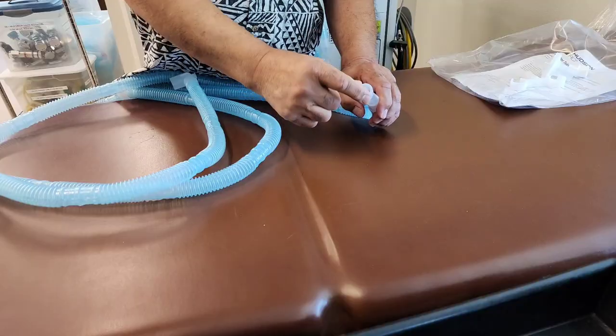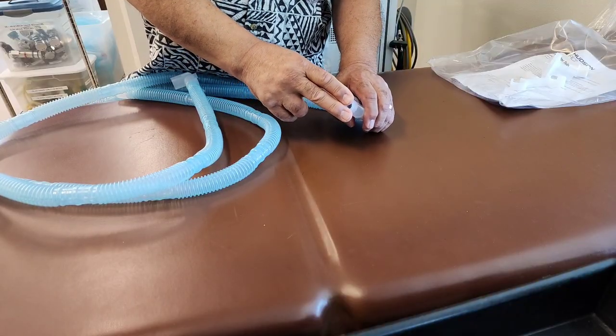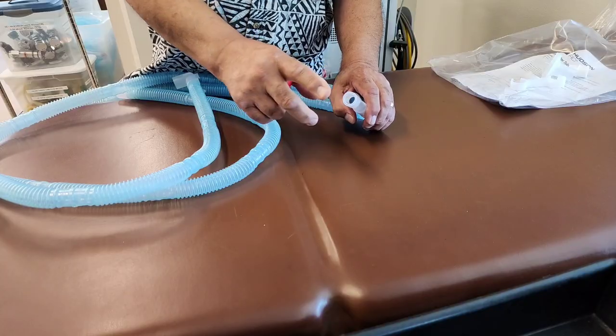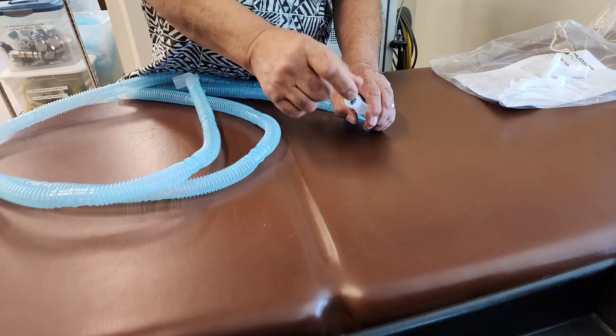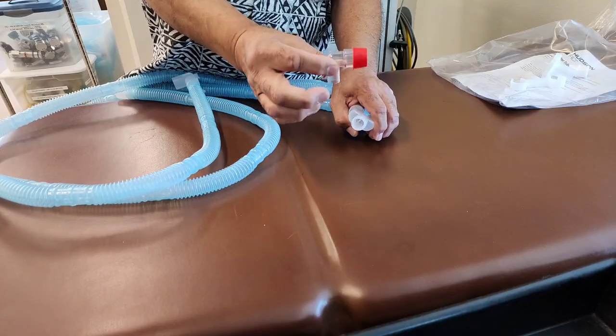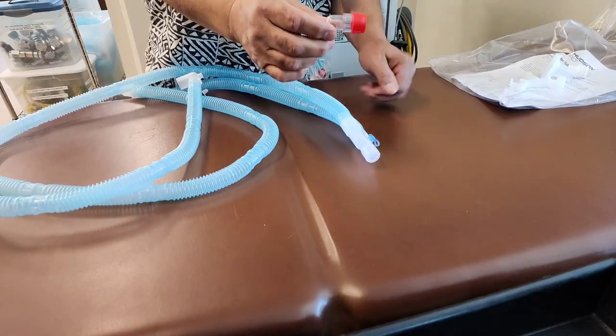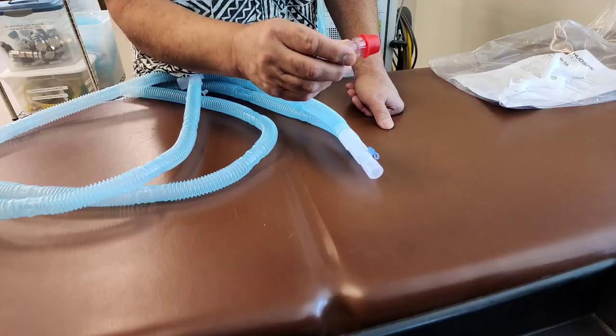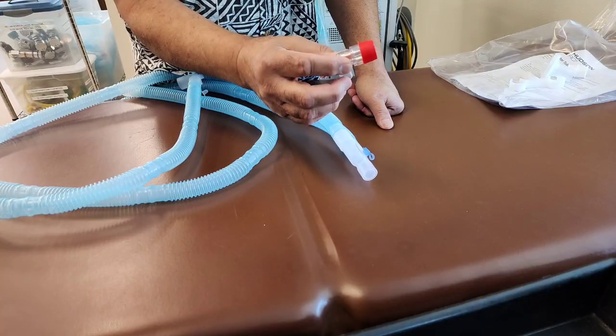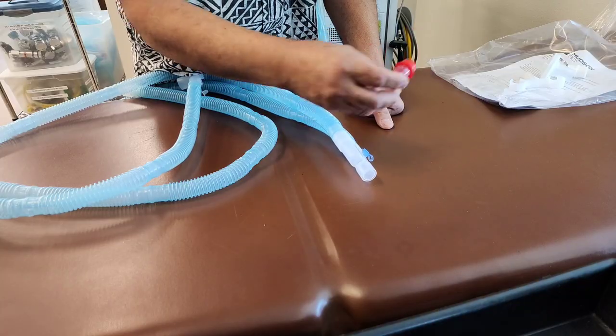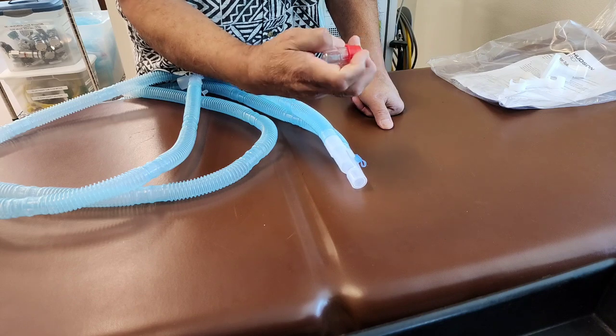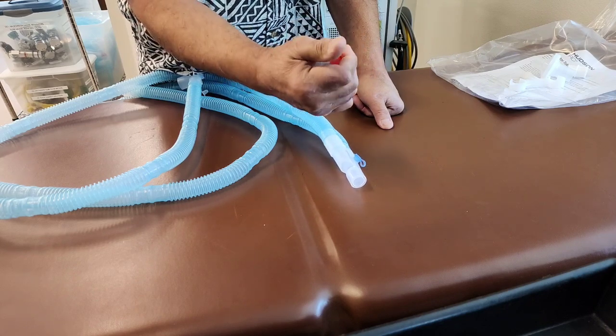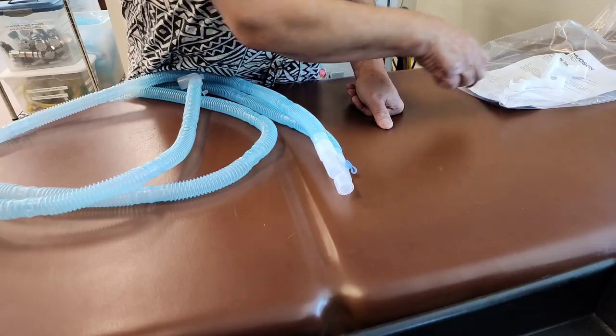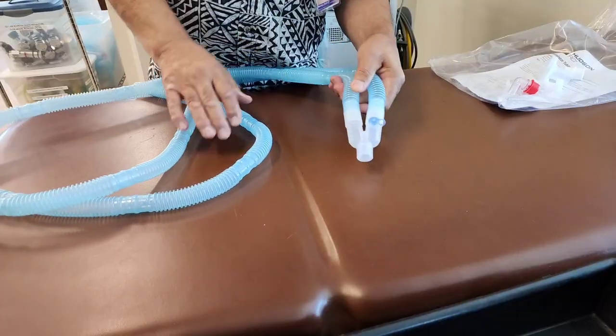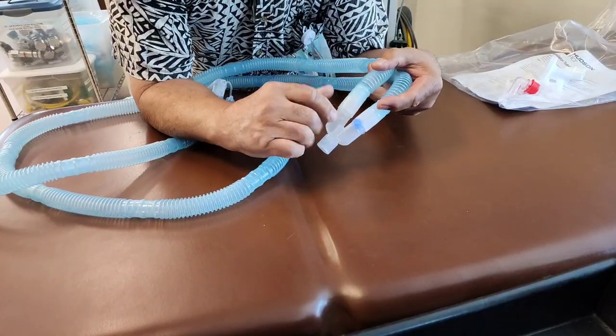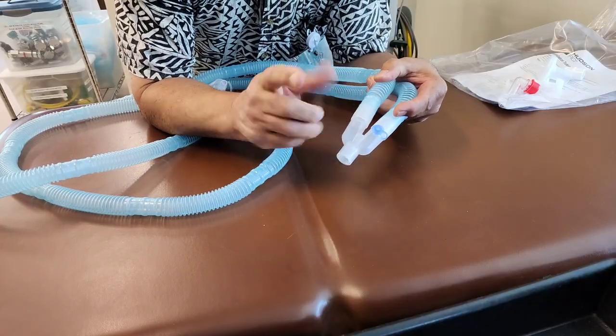There'll probably be an HME, which is a heat moist exchanger, that's attached here, maybe a little flexible tubing, and then it'll connect with something like this. This is not designed for putting on a patient because this doesn't move around, but it's an attachment for the endotracheal tube or tracheostomy tube. This is used when we have to do a system test to check for any leaks in the circuit, and we'll do that later. Put that aside.